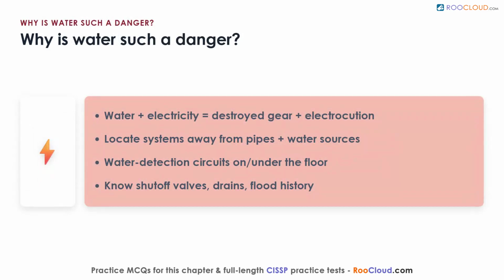So why is water such a danger to your systems? Because water and electricity together mean destroyed gear and a real risk of electrocution. Leaks are rare, but when they happen, the damage is severe. So locate server rooms and critical equipment well away from pipes and water sources. Install water detection circuits on the floor or beneath a raised floor, so an alarm sounds the moment moisture creeps toward the racks. Know where your shut-off valves and drains are before you ever need them.